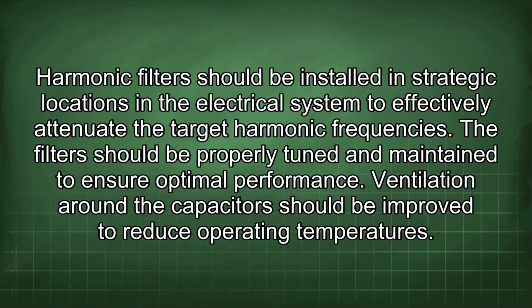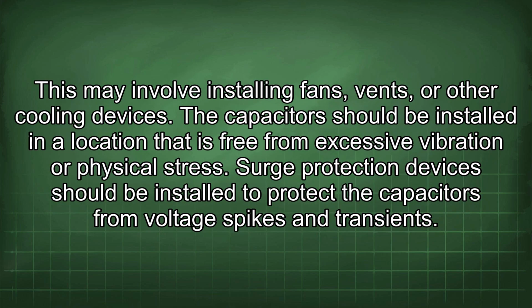Ventilation around the capacitors should be improved to reduce operating temperatures. This may involve installing fans, vents, or other cooling devices. The capacitor should be installed in a location that is free from excessive vibration or physical stress. Surge protection devices should be installed to protect the capacitors from voltage spikes and transients.